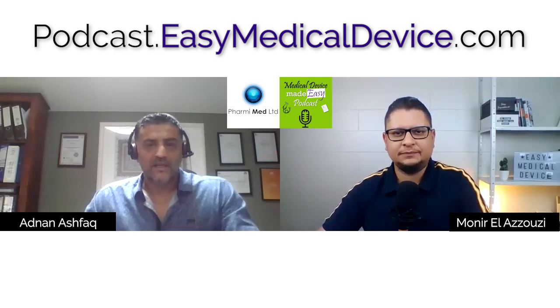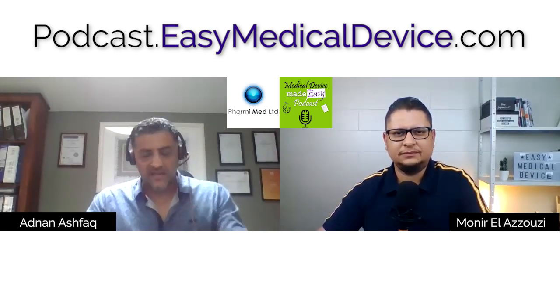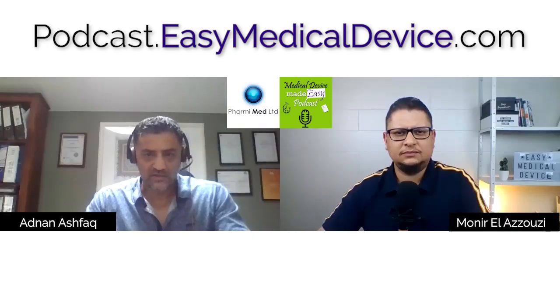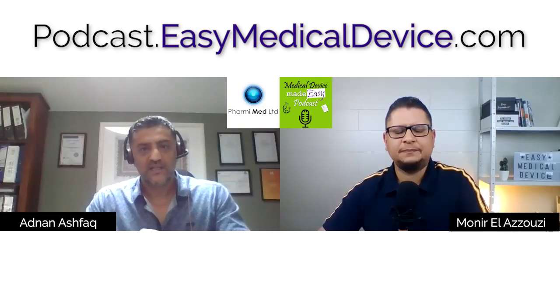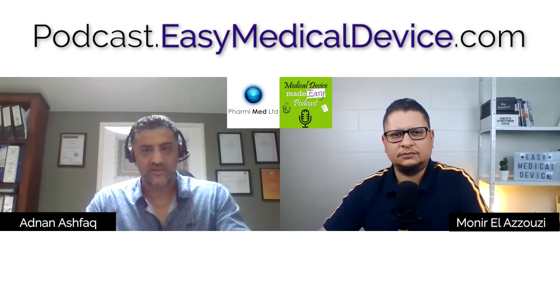Well, I think the main thing every manufacturer needs to do, software or no software, is the fundamental thing which I always advise manufacturers: make sure that you know your intended purpose. The intended use and intended purpose drives everything, and that is so important, because the first thing the manufacturer has to do is ask, do we qualify as a medical device? Does it have a medical intended purpose? Is there a clinical safety or clinical benefit?